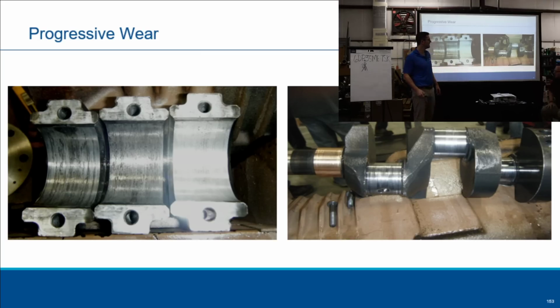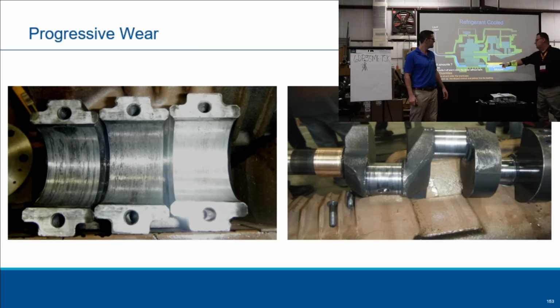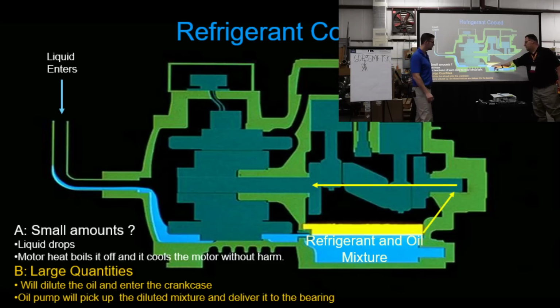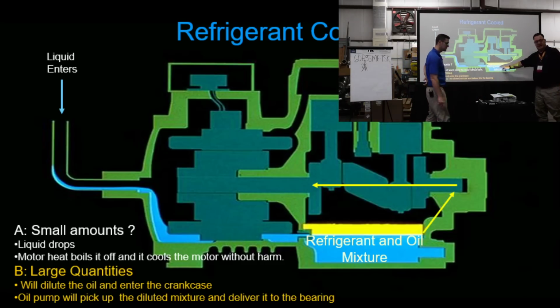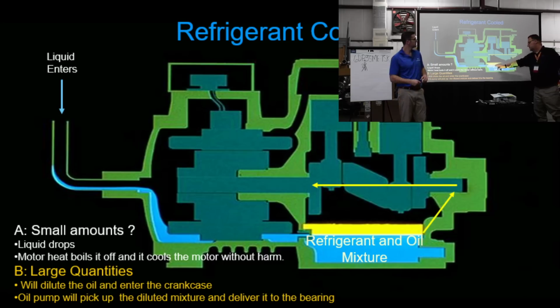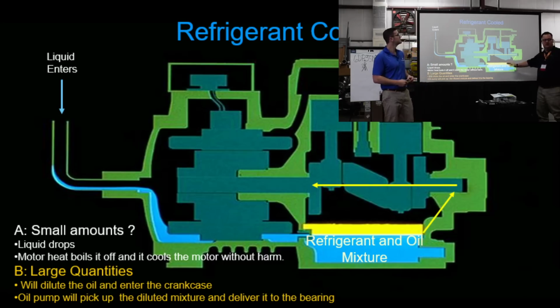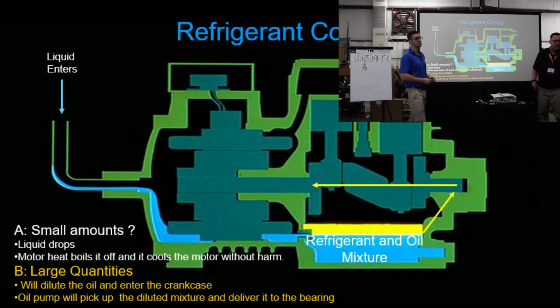Go ahead, Don. I just want to back up one slide here. So again, this is an open check valve, but what this blue indicates is liquid refrigerant coming back on this refrigerant cooled. It's heavier than the oil. The oil is showing you the oil itself, okay? The reason I point that out is that tube, the pickup tube that Trevor was talking about earlier, that's down here. Now it's pulling up mostly liquid refrigerant, as Trevor said, okay? That's what's going on there. Okay? Thank you, Don. Yeah, exactly.